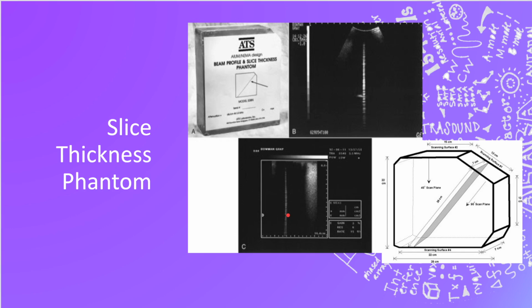Continues to be narrow until the focus, which we can see here. And then we can see how it diverges in the far field. So this phantom helps us to determine what our elevational resolution is and what our lateral resolution will be.